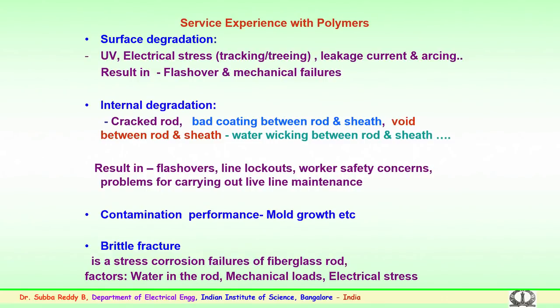So, this could again result in flashovers, line lockouts or blackouts, partial blackouts as we call them. Apart from this, it could also cause worker safety concerns, as the methods for carrying out live line maintenance are not fully developed; they are being developed for these insulators. So, this internal degradation could also cause serious safety concerns for the utility engineers during maintenance.